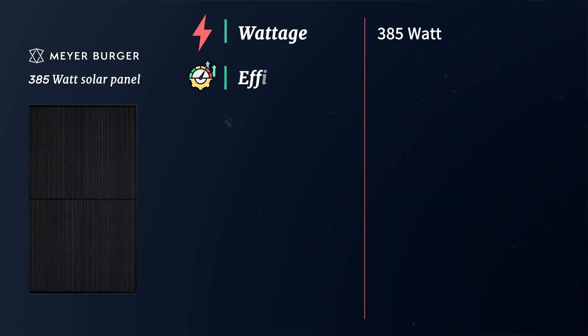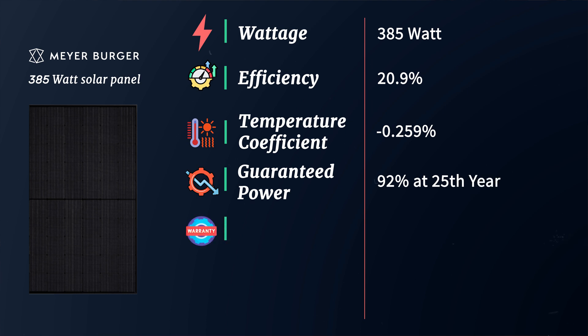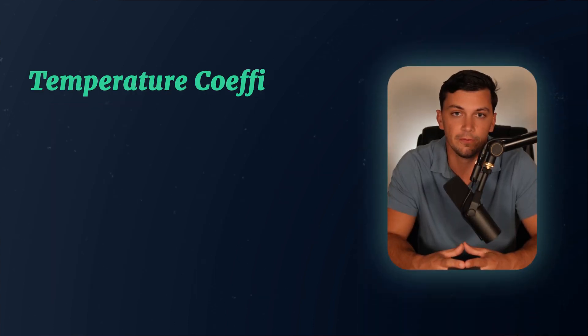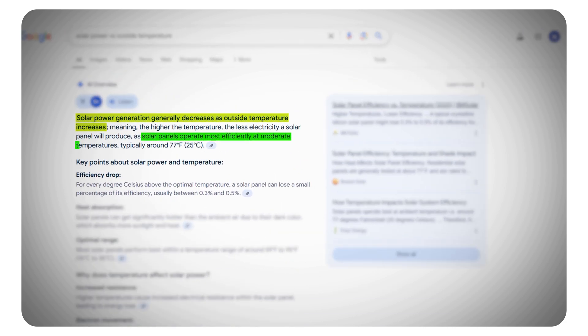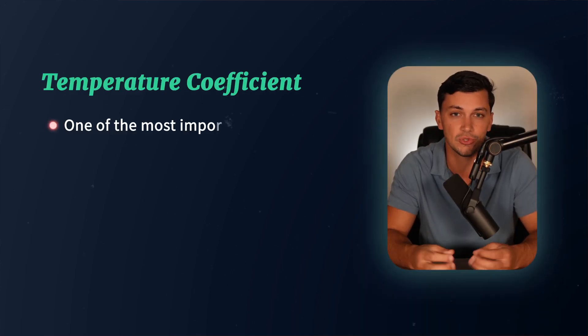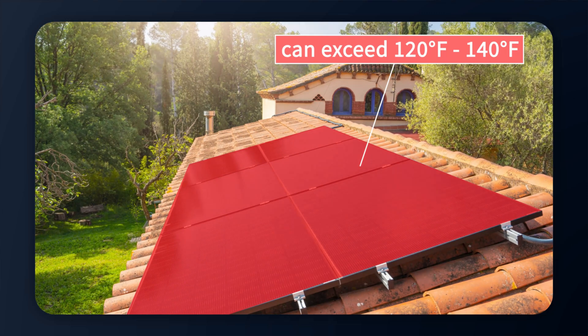The 385 watt Meyer Burger black panel offers an efficiency of 20.9%, a temperature coefficient of negative 0.259%, and guaranteed power of 92% at year 25. They also offer a 25 year product warranty. The X factor is that it's a great panel for tropical climates like Florida, which deal with high heat and extreme weather. Temperature coefficient refers to how well the solar panel produces when temperatures are not optimal. Panels produce at max power at 25°C (77°F), and for every degree above that, they're slightly less efficient. In summer, roof temperatures can exceed 120 to 140 degrees, drastically impacting power output.